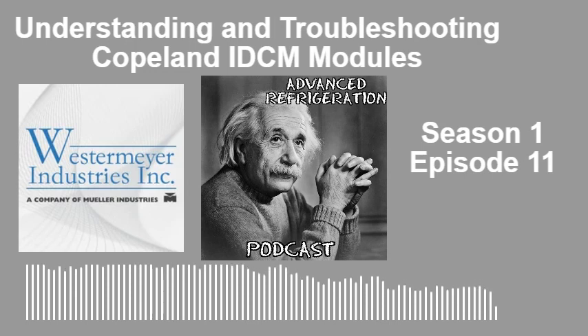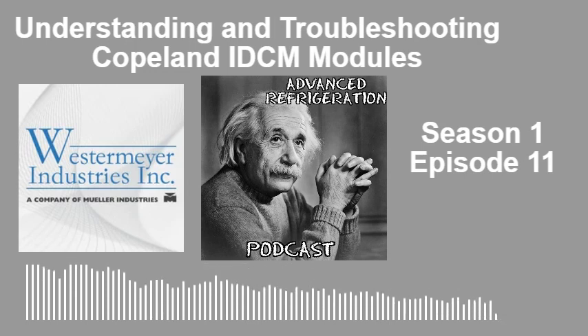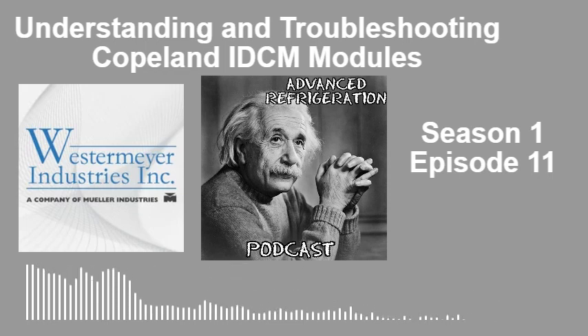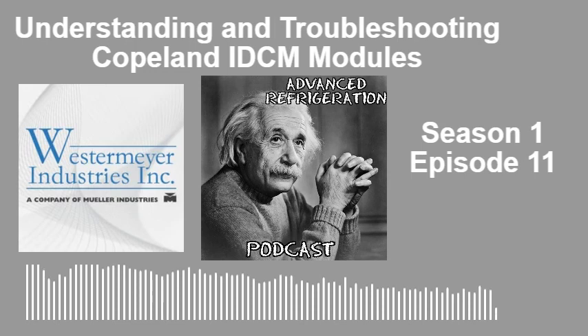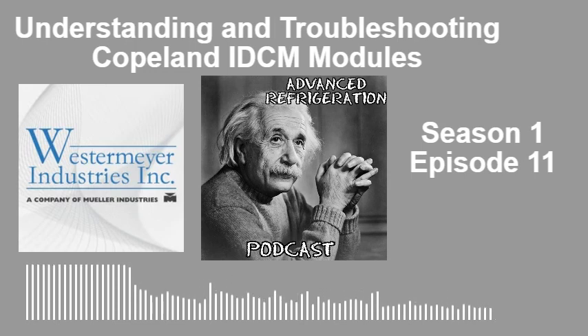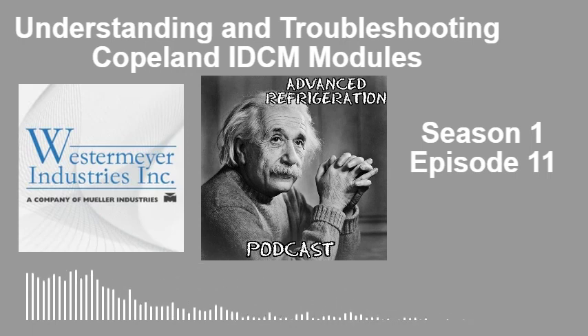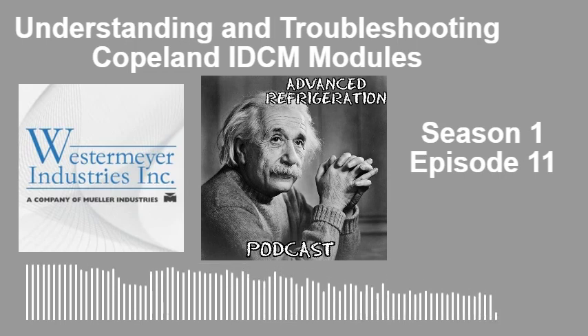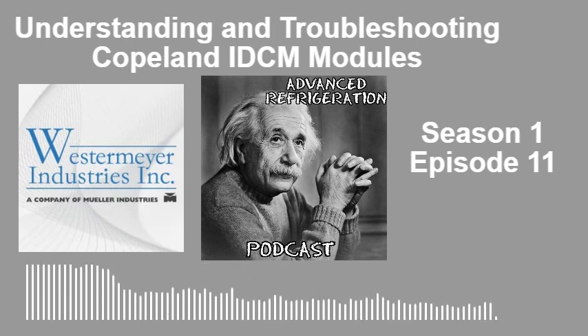Each one of these controllers has its own part number, so you need to pay attention to that. If you're working on a 3D, you need to make sure it's the 3D and scroll one. And if it's a 4D or a 60, you need to make sure it's that one, because A, your voltages aren't going to match for your signals, and B, it's just not going to work properly. On startup, I've seen that a couple times where they've had the wrong ones.